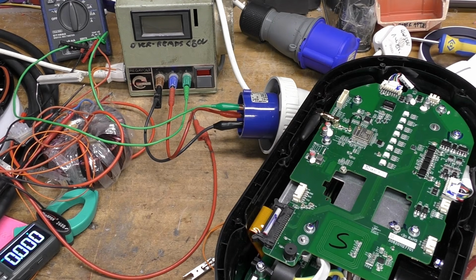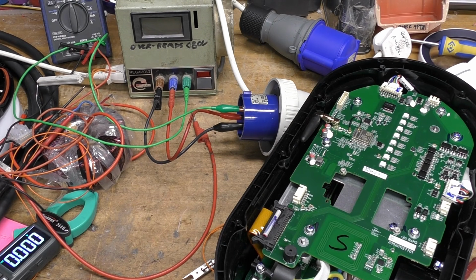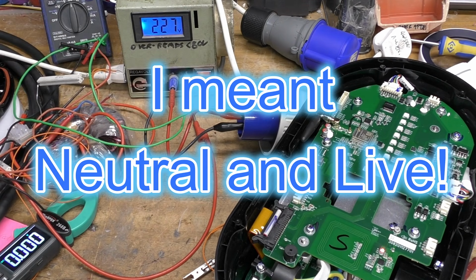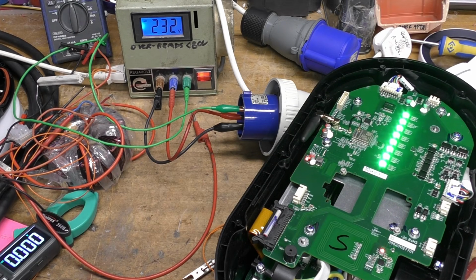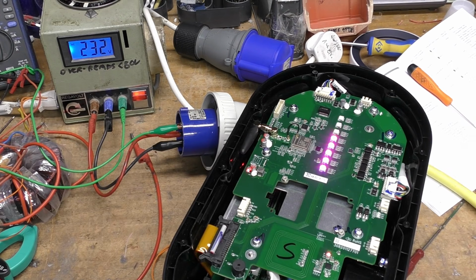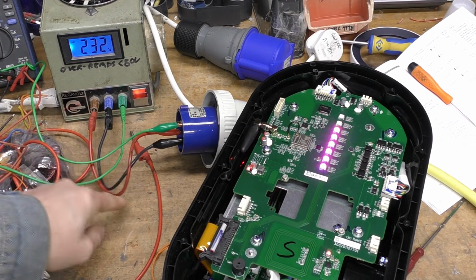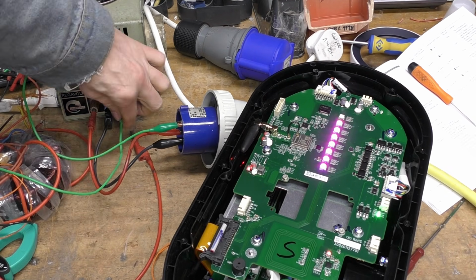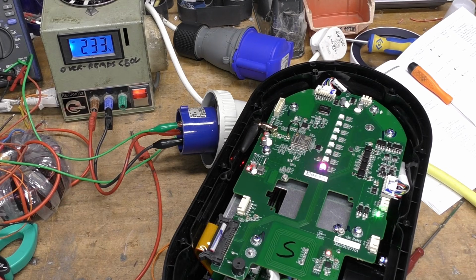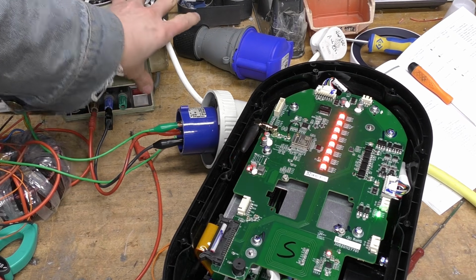Now, another way of detecting PEN faults is the voltage between neutral and earth increasing. So a very quick test of that: I'll just swap the neutral and earth connections and see what happens. It's starting up, and now it's gone into a fault mode. And let's just see what happens if we just lose the earth connection. Again, we're going into error mode, which is good.